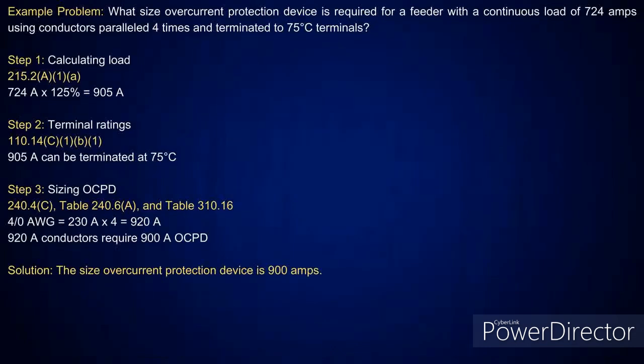Now, here's a feeder. Now, I brought this up. I said, when I get to a feeder, it doesn't matter. If it's continuous, I'll take it at 125%. It's just larger numbers. And in this case, I'm going to parallel it four times and terminate it to 75 degree C terminals. So I'll calculate the load once again. And if you look at 215.2(A)(1)(a), that's for conductors there. So I take 724 amps times 125% gives me 905 amps.